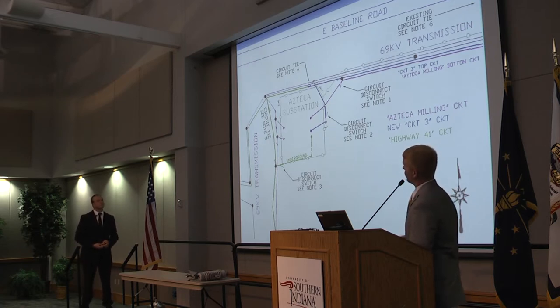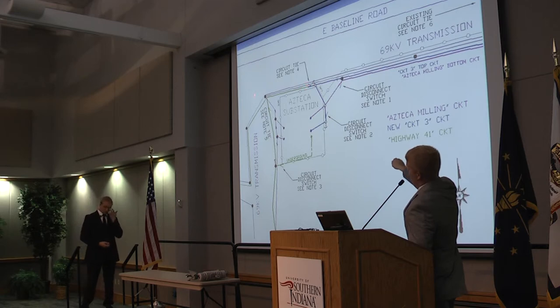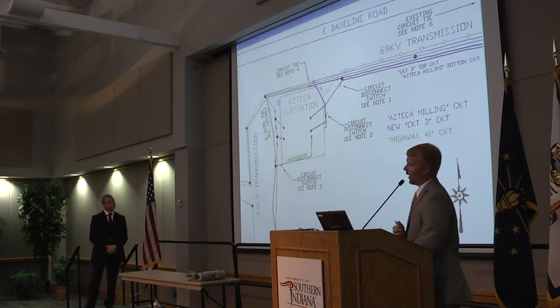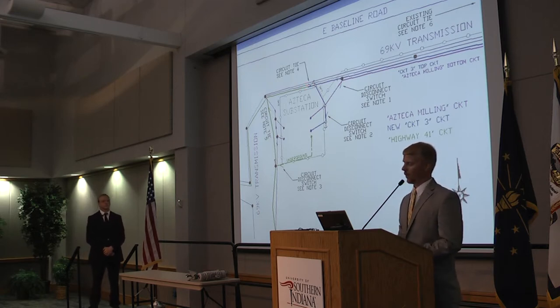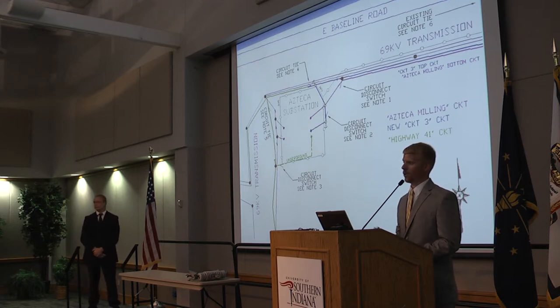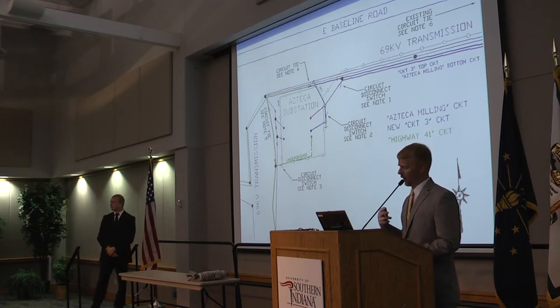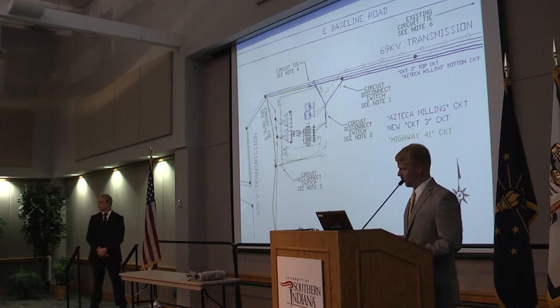What circuit ties allow us to do is, if there is an outage or if we need to open a disconnect switch, we can actually feed from a different direction. So if this was open, then this line would not be fed anymore. So we could use this disconnect switch, or this circuit tie switch, and close that in, and this would all continue to be fed. It's not a permanent fix, but it does help with switching and keeping people on power as much as possible.